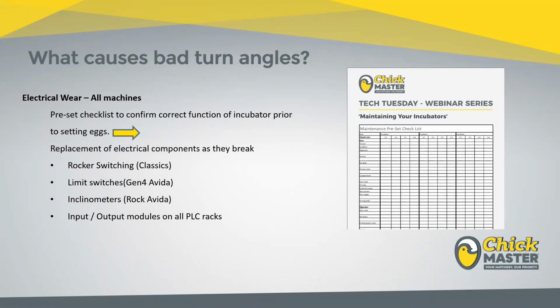From my point of view, prior to any eggs being set in an incubator, that incubator belongs to the maintenance crew of the hatchery. It's their responsibility to make sure that everything on that machine is fit for purpose before it's handed back to the hatchery staff for eggs to be loaded. That's just a simple case of going through the engineer's menu and testing each of the functions, measuring the turn angles, making sure your cooling works, making sure your heating works. And if you spot a problem at that stage, it can save you potentially tens of thousands of pounds in egg losses a couple of days down the line.